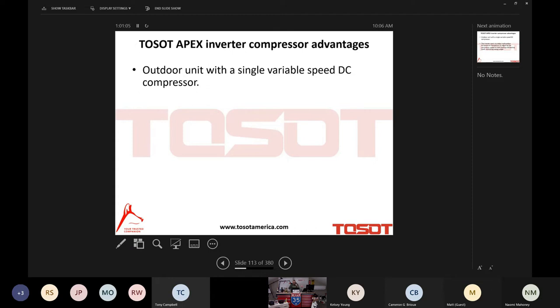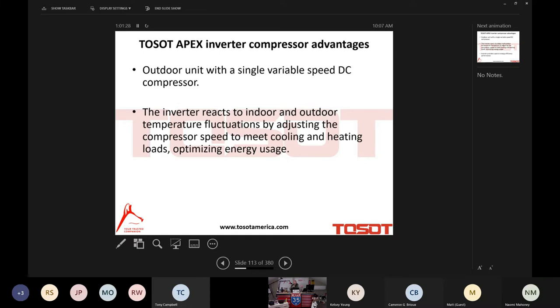And for those of you who are familiar with a frequency drive and what it does, very expensive and another piece of equipment. So that's why the entire industry, not just Tosot, but the entire inverter industry, all utilize this simulated DC voltage compressor, because you can modulate it without a frequency drive.